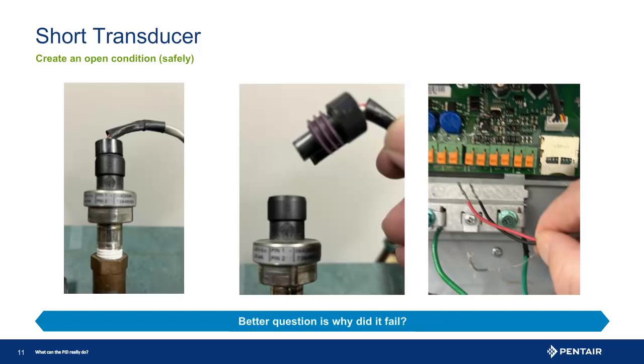Start, reset, then run the drive. What fault shows? If the short fault condition appears again, the issue would be the drive. If an open fault appears, replace the transducer wire. See, no meters. And again, why did the failure happen? Installation can make or break a system.